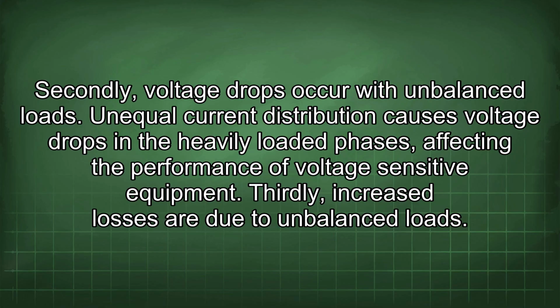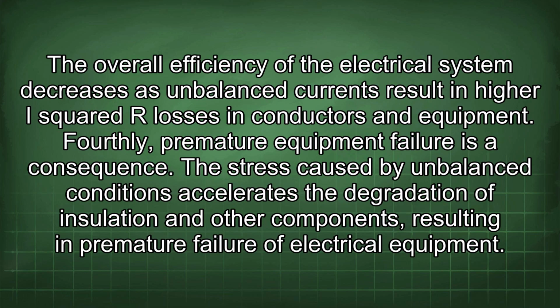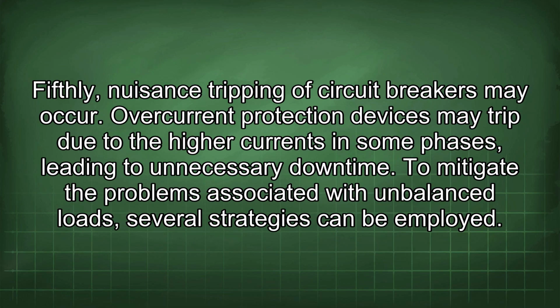Thirdly, increased losses are due to unbalanced loads. The overall efficiency of the electrical system decreases as unbalanced currents result in higher I²R losses in conductors and equipment. Fourthly, premature equipment failure is a consequence. The stress caused by unbalanced conditions accelerates the degradation of insulation and other components, resulting in premature failure of electrical equipment. Fifthly, nuisance tripping of circuit breakers may occur. Overcurrent protection devices may trip due to the higher currents in some phases, leading to unnecessary downtime.